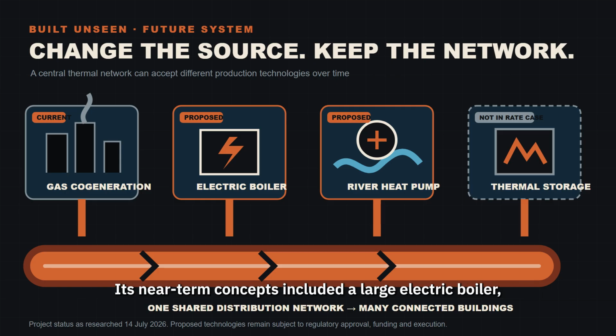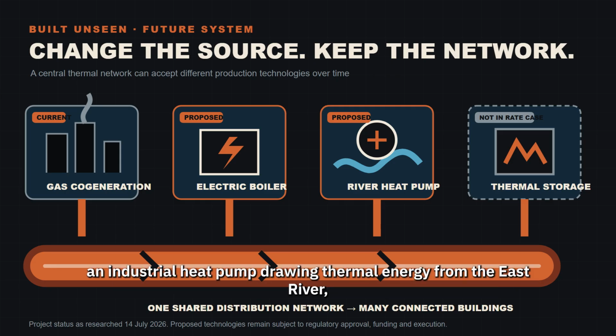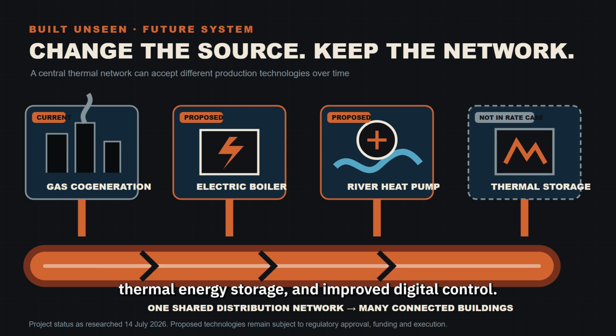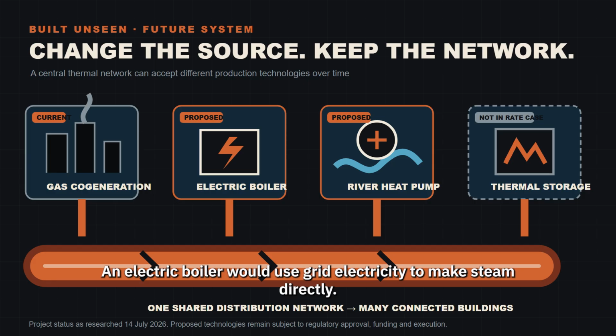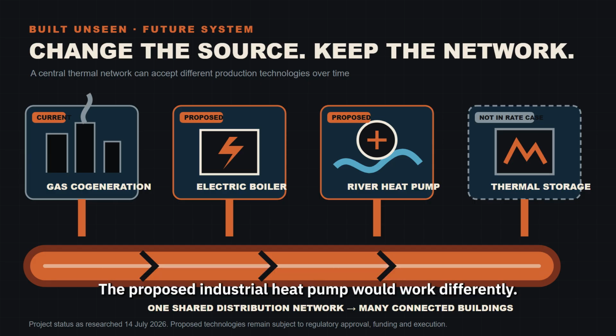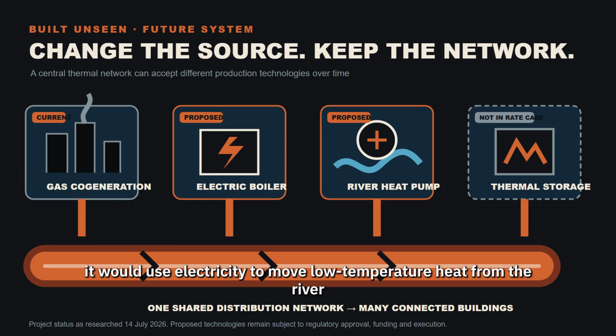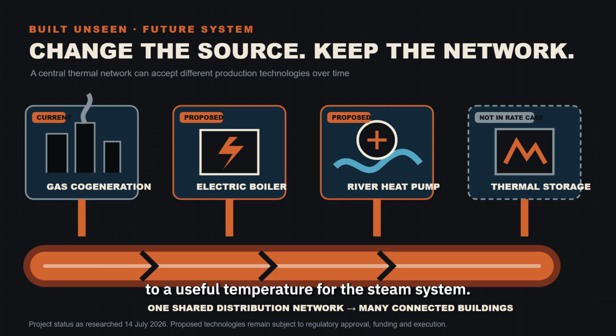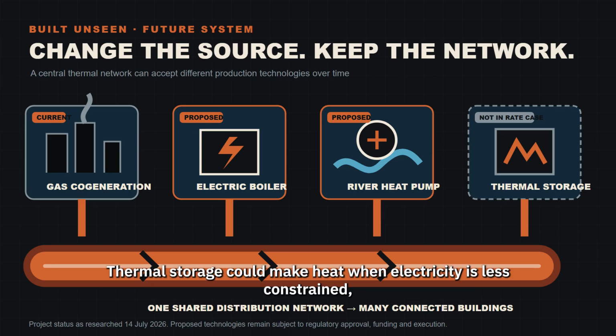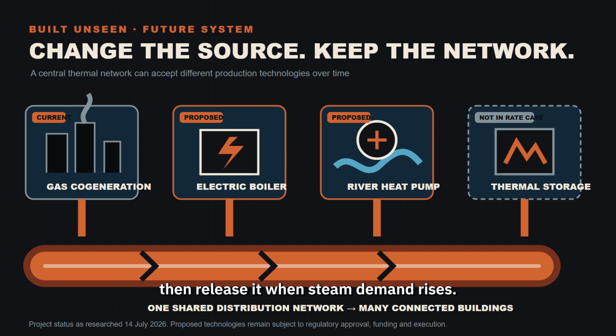Its near-term concepts included a large electric boiler, an industrial heat pump drawing thermal energy from the East River, thermal energy storage, and improved digital control. An electric boiler would use grid electricity to make steam directly. The proposed industrial heat pump would work differently. Rather than creating all its heat through electrical resistance, it would use electricity to move low-temperature heat from the river to a useful temperature for the steam system. Thermal storage could make heat when electricity is less constrained, then release it when steam demand rises.